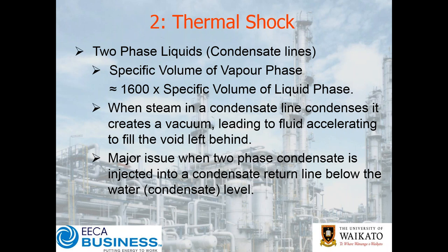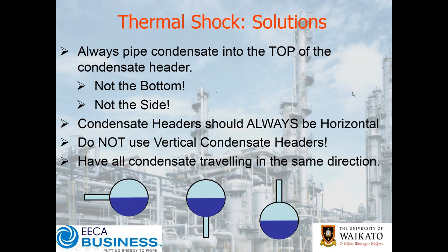It's not a very friendly percolator, because as you percolate that through the steam is going to want to condense. But if any of that steam is superheated — which can be the case if you've got different pressures at work — you can end up with flashing off some condensate in the pipe. Instead of talking about flash steam, if we talked about an uncontrolled explosion of condensate into vapor and think about that occurring in our condensate line and the damage that can cause — it becomes very, very important.